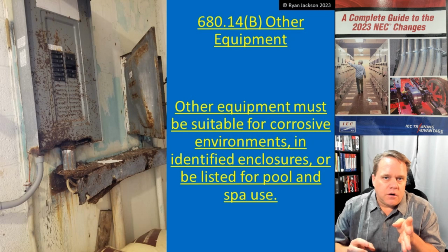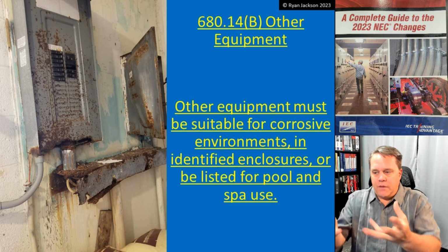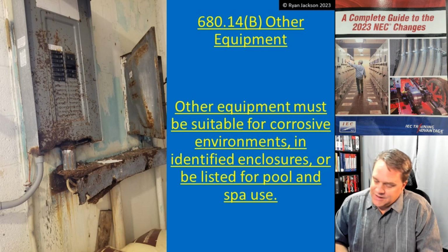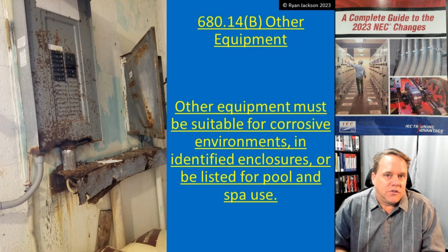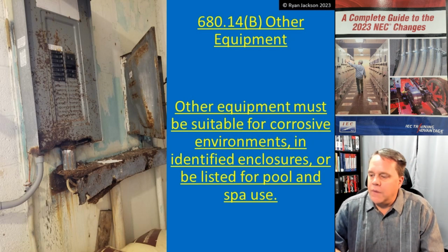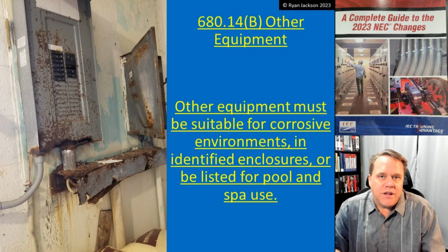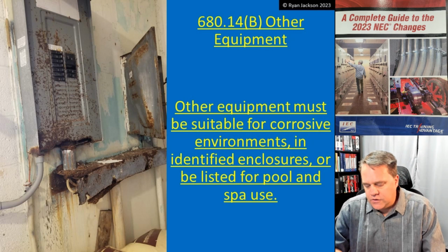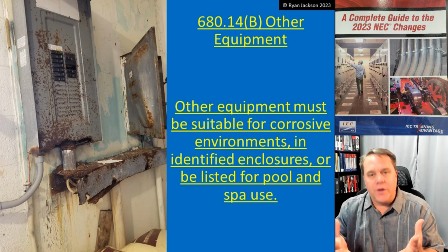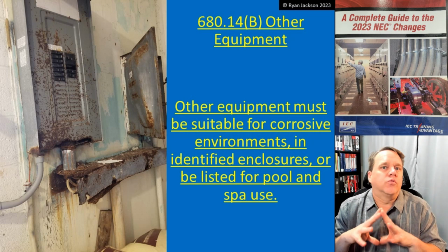This photograph here is in a swimming pool equipment room. And you can see by the state of the equipment, it's rotted away to nothing. Again, I'm embarrassed to admit this, but I've inspected installations, and past installations, that are probably going to end up looking like this. And that was my fault, and I screwed that up. If I could go back in time, I would change it. But all I can do now is tell you that I screwed it up, and that maybe in the past you have screwed it up too, but we need to stop screwing up. We need to make sure that we're installing swimming pool equipment in equipment that's rated for the environment.